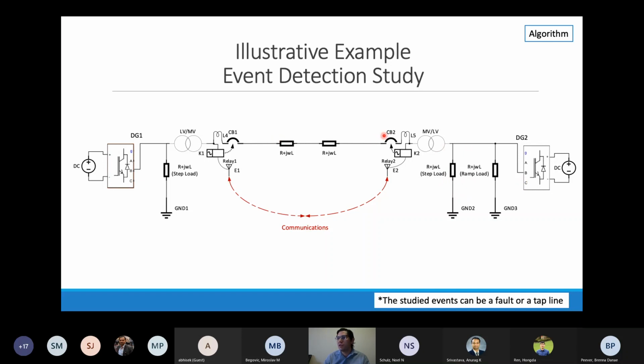And here we have a shared load current, and these relays should be able to talk to each other in order to detect a fault. So our method, developed before, is based on the cosine and sine of the angle, which is basically the rate of change in a fault or in any other event.